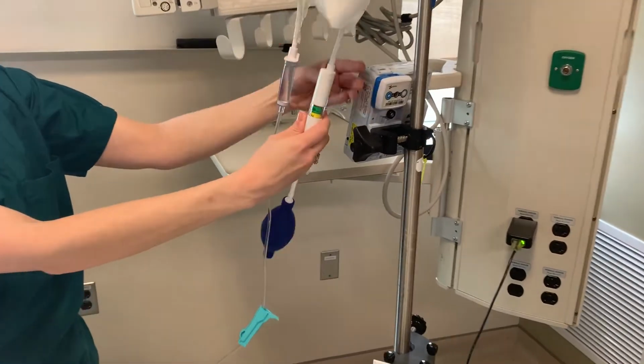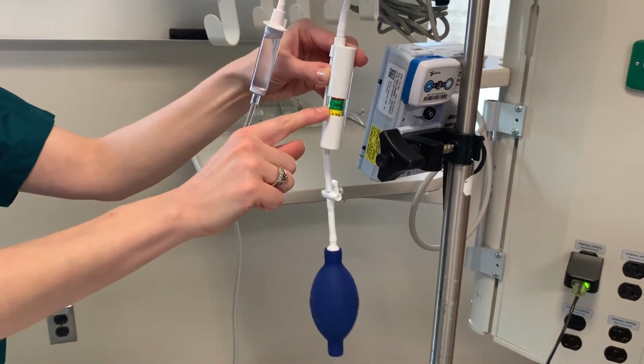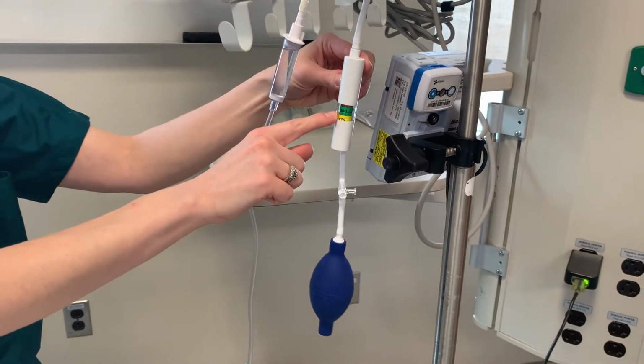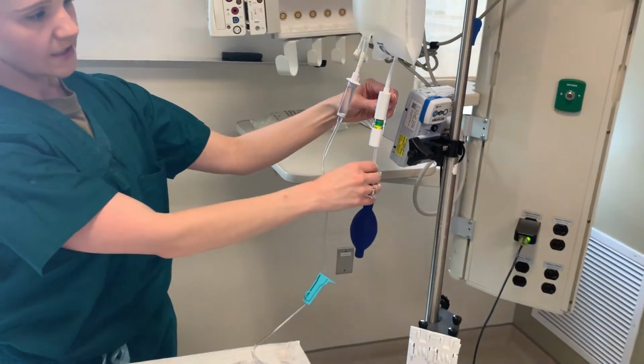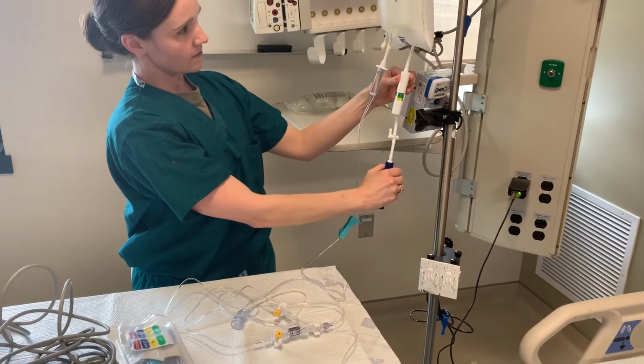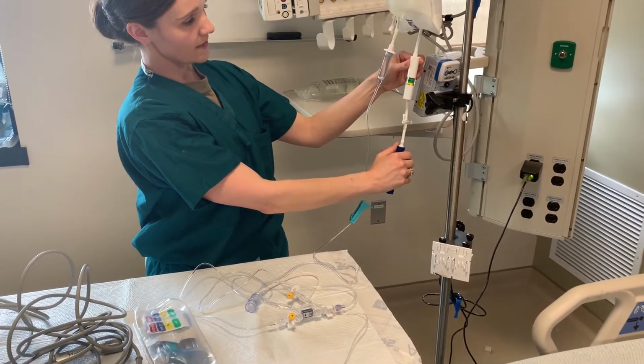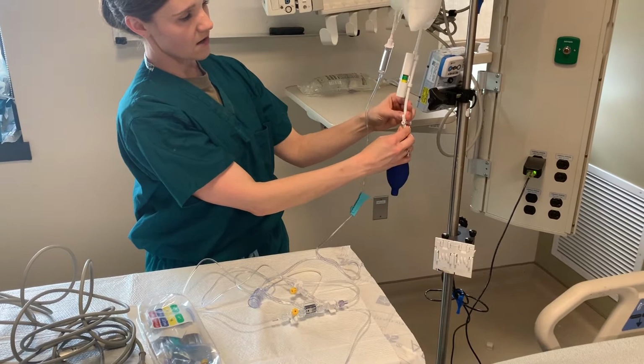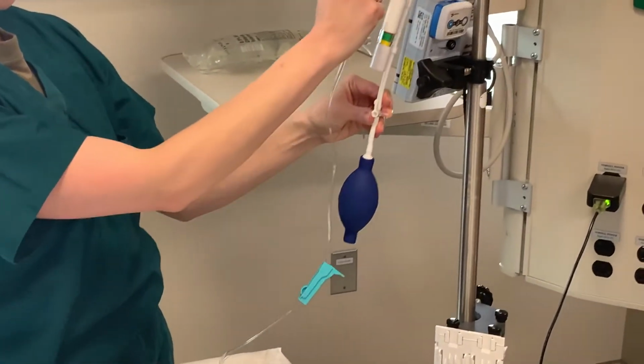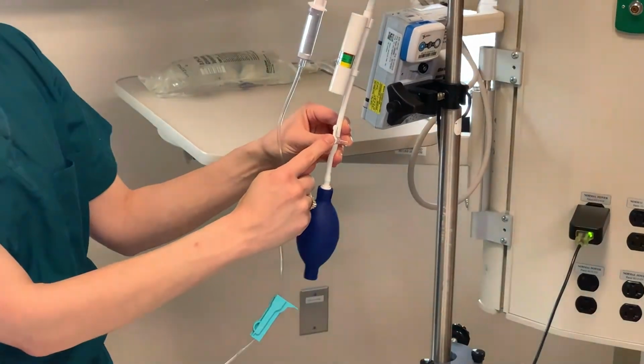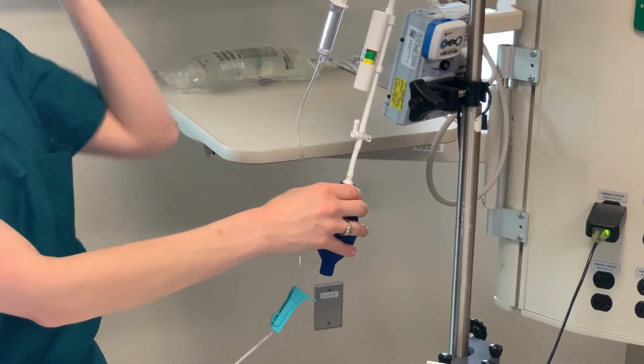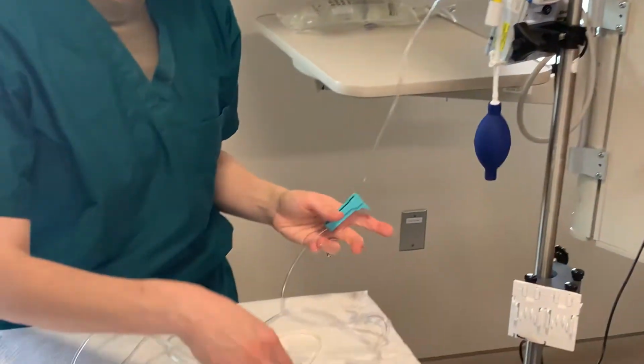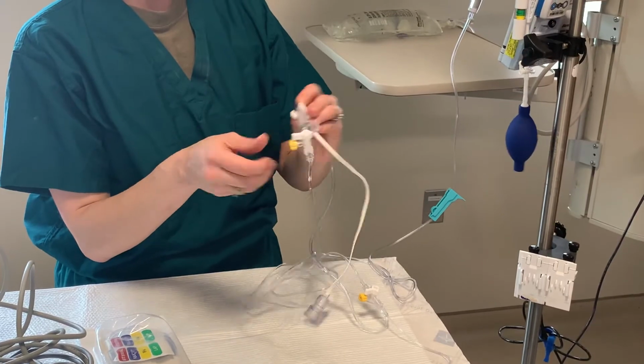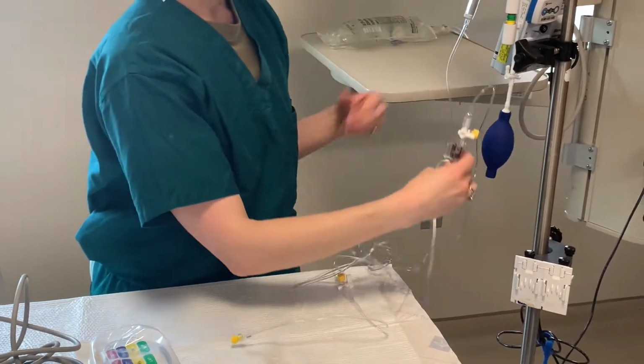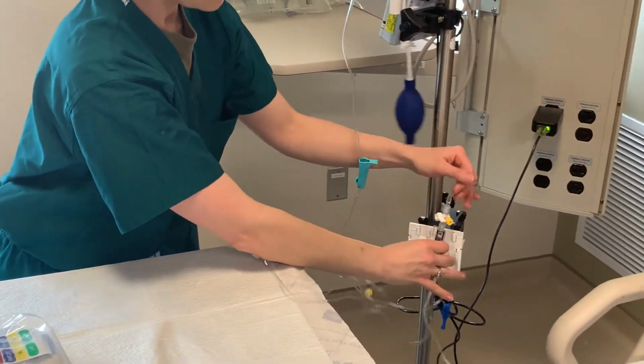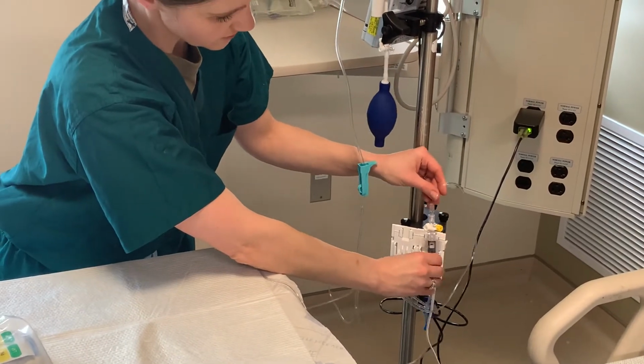After you spike your fluid bag, you can increase the pressure bag here, pumping the bulb up until you reach approximately 300 millimeters of mercury of pressure, or the green color is a good indicator. After you're done pressurizing the bag, you will turn the stopcock off to the bag, or in the up position. After you pressurize your bag, you will take your transducer here and put it on the holder approximately level with the patient's heart.